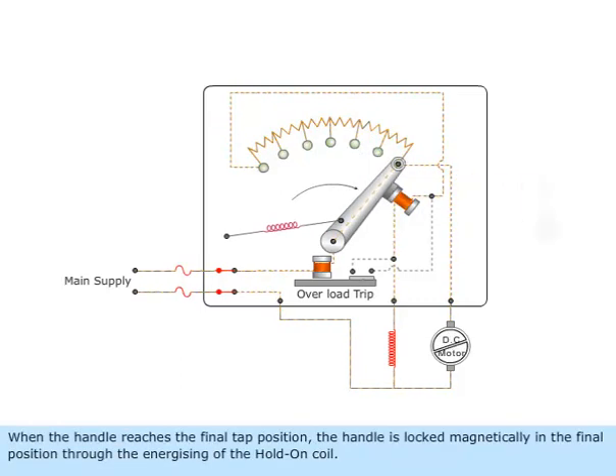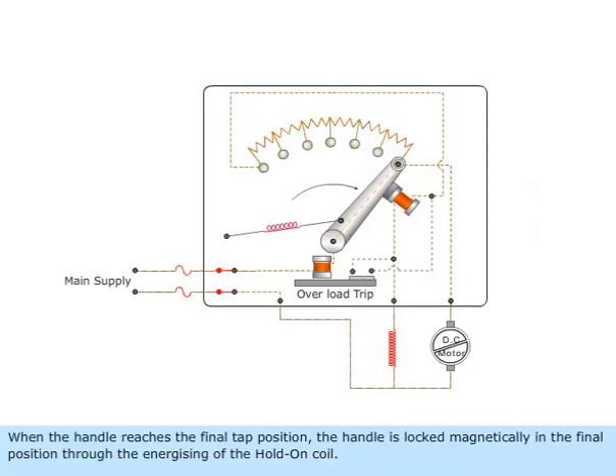When the handle reaches the final tap position, the handle is locked magnetically in the final position through the energizing of the hold on coil. The motor runs now at normal speed.